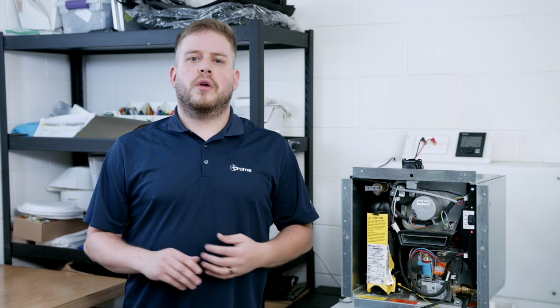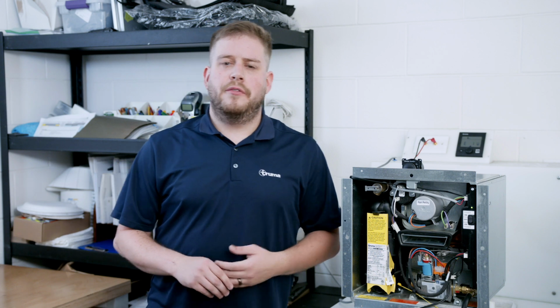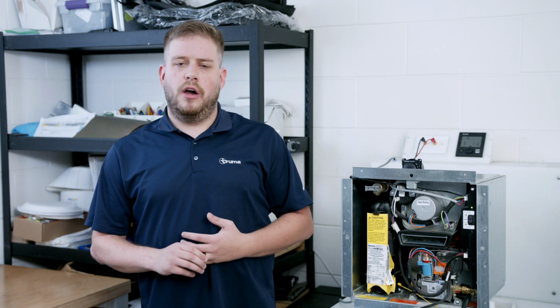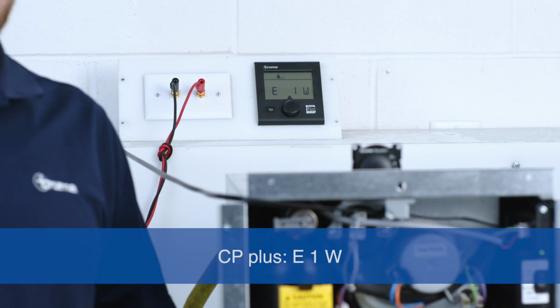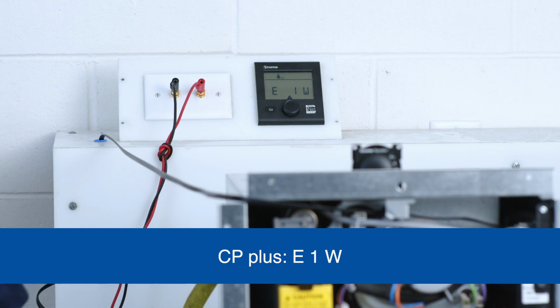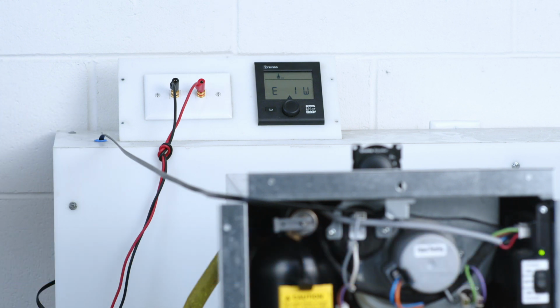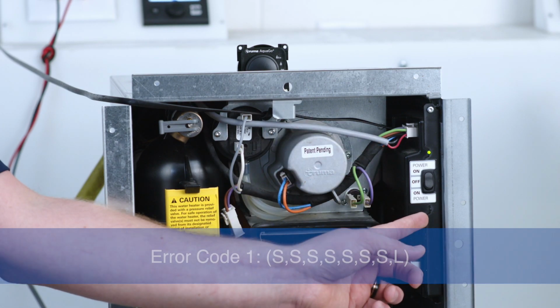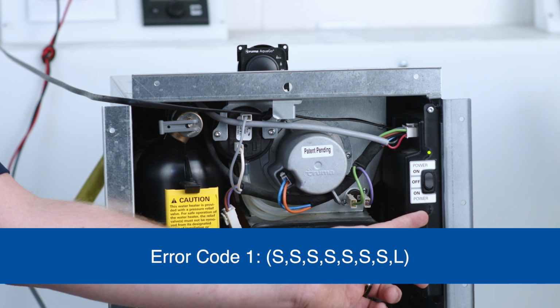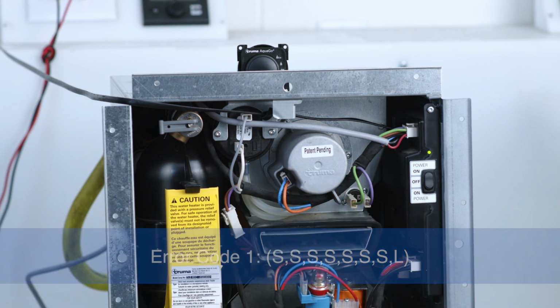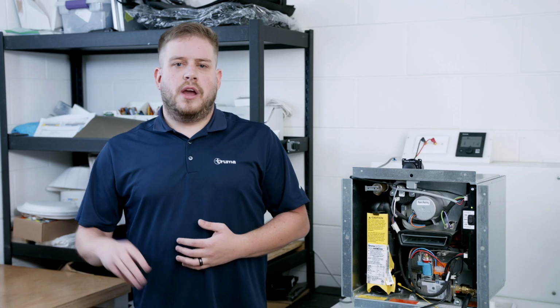The first error code we're going to be going over is error code 1, flame not detected by the AquaGo. On your CP Plus, the E1 error code is going to display as E1W. The board will flash 7 shorts and 1 long to display the E1 on the dial control. That means it has tried 3 times to light and has not been able to establish flame within the burner.